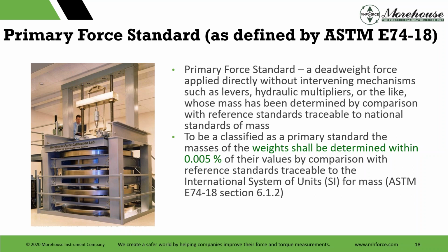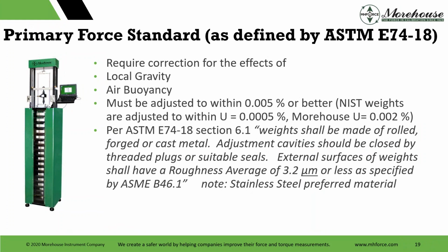Hey, there we go again, SI, not traceable to NIST, for mass, ASTM E74, that's section 6.1.2 if you want to read it. And they require correction for the effects of local gravity and air buoyancy, and weights must be adjusted to 50 parts per million or better. NIST weights are adjusted to within 5 ppm or 0.0005%. Morehouse, we're typically better than 0.002%.